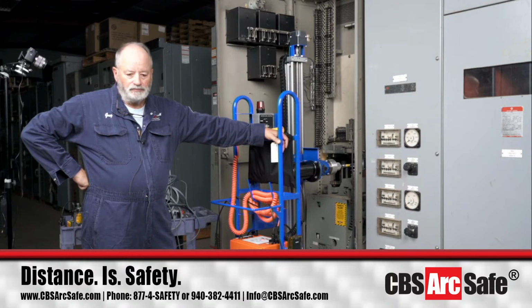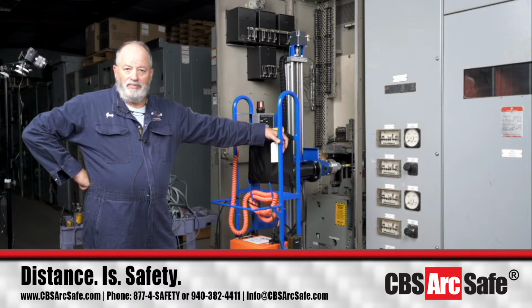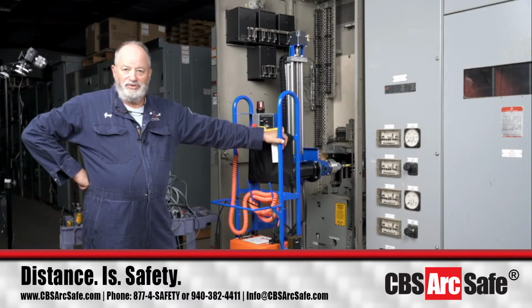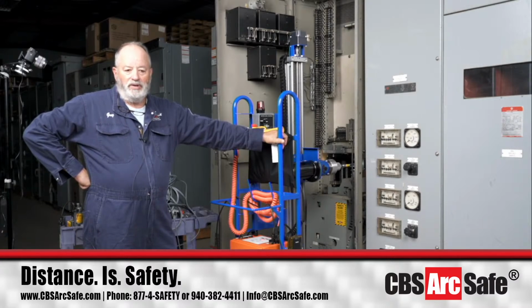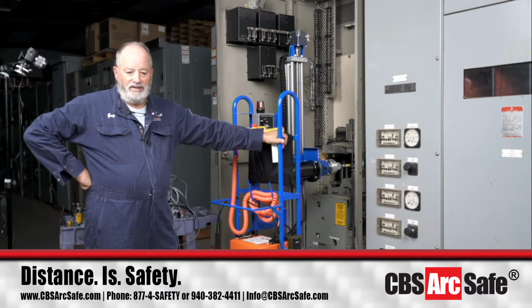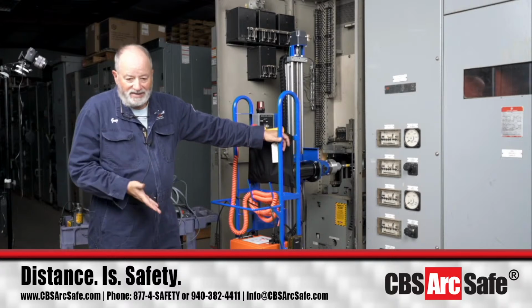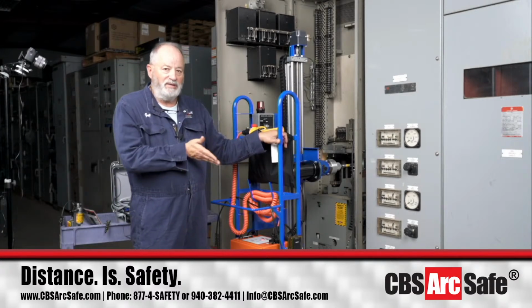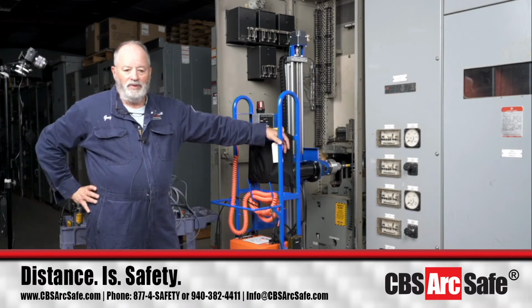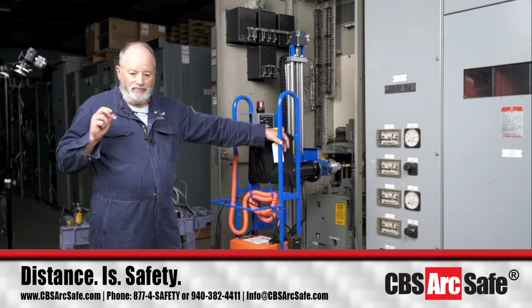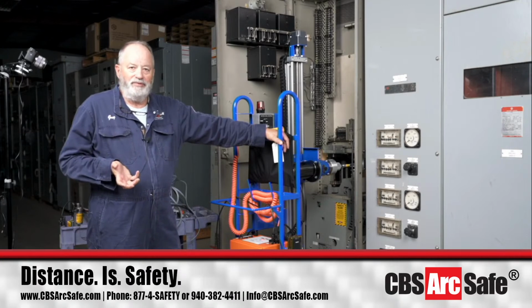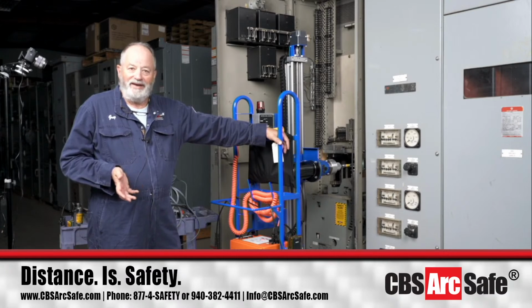The breaker won't move. I took out the input settings and put the unit in what we would call beast mode, where it's just like we're going to let it run to its operating limits, where we could generate potentially 40 foot-pounds to get a breaker out. So when I did that, you heard, because whether a man did this or the machine did it, the same thing was going to happen when this breaker broke loose. So you heard the bang as far as the release of energy in this bound up racking mechanism, and everybody behind me in this power plant just started to laugh.